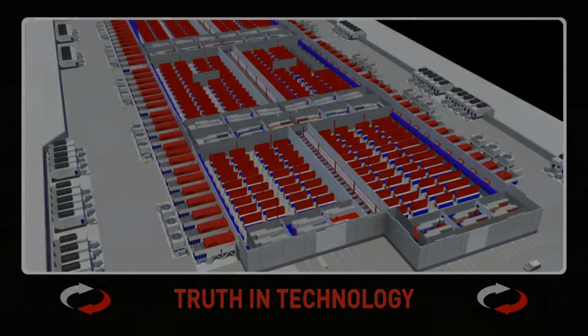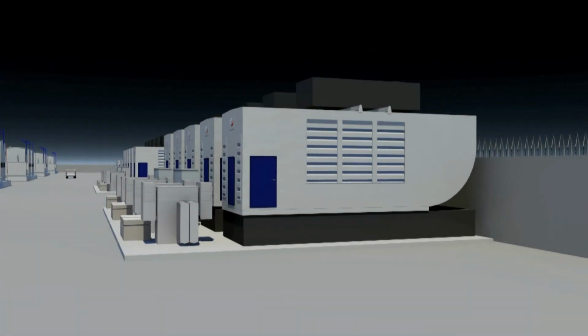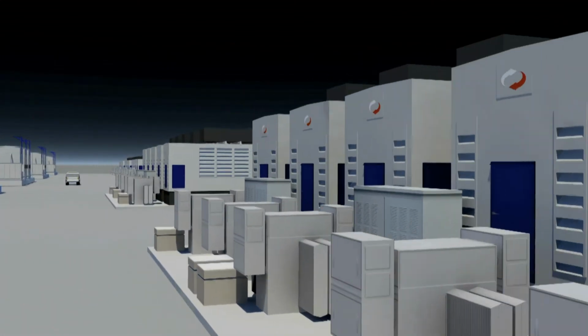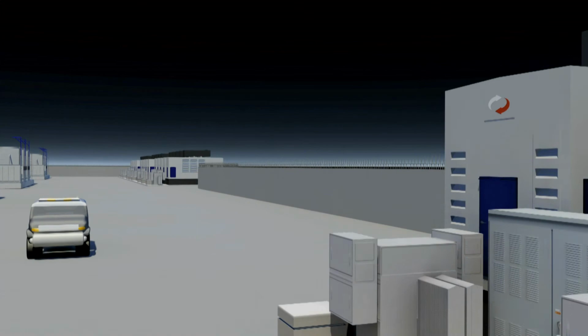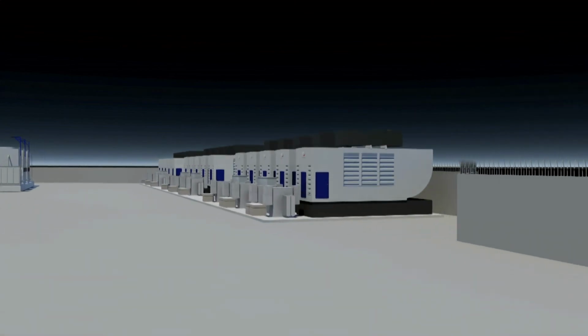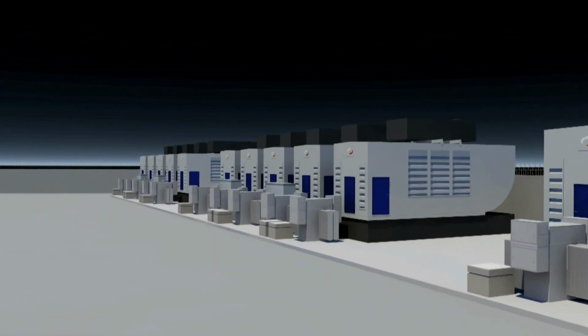Now, the other element that's critical is this environment has to be up 100%. On the outside of the data center is our generator set. At full build out, we'll have 50 2.8 megawatt diesel generators, for a total of 140 megawatts of generating capacity.